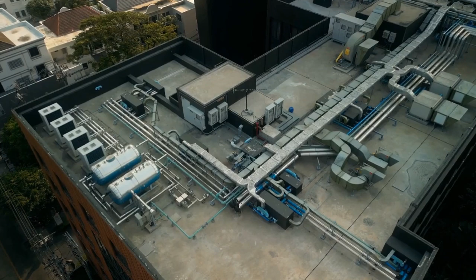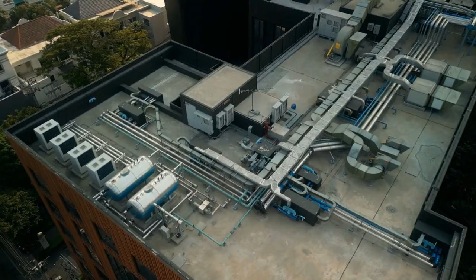So when there's complex systems, there can be energy savings in every stage, right from the condenser on the rooftop through to the registers, the duct registers that push cold air into the room. So there's going to be opportunities probably with the cooling tower fans, the condenser water pumps, the condition of the cooling tower itself, the chiller itself, the chilled water pumps, the air handling units, then the distribution of air, supply of fresh air. And the opportunities are not just with the equipment, not just replacing bits of equipment, it's how the equipment is configured, controlled, how it interacts with each other.